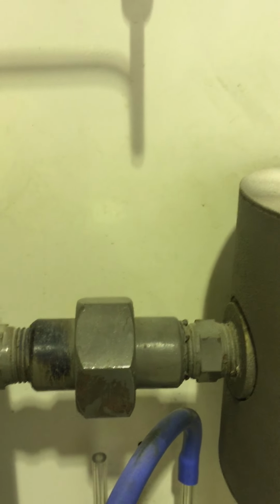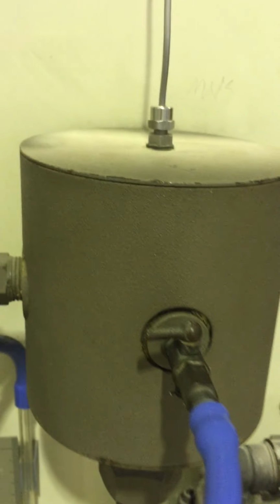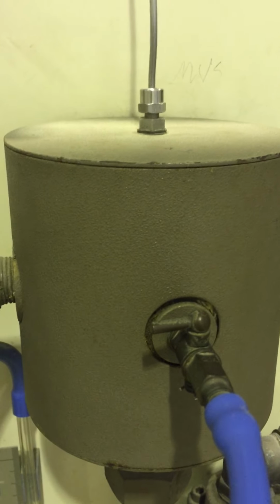Then the steam leaving, assuming it is dry steam according to the separating calorimeter, will be MVS, mass of dry steam leaving the separating calorimeter. But we'll find out that actually the steam is not really dry steam in here. It is still saturated steam. So that's why we need the throttling calorimeter to make a more accurate measurement of the dryness fraction.